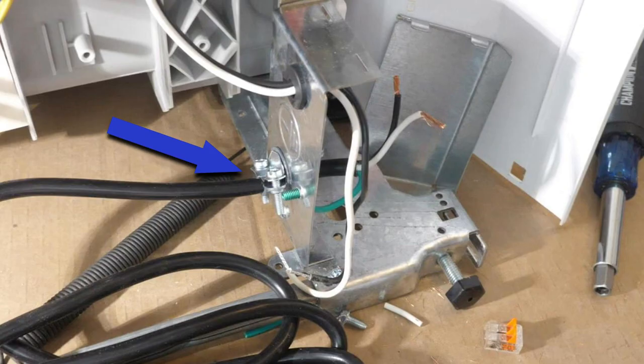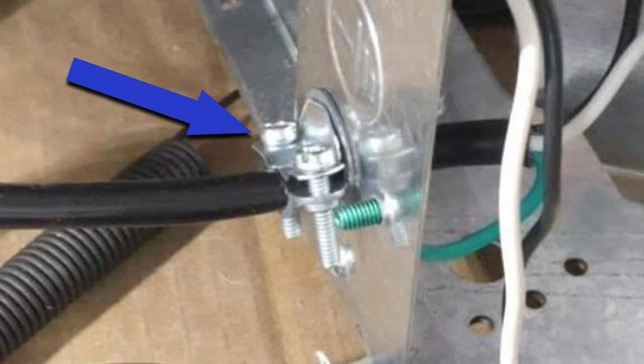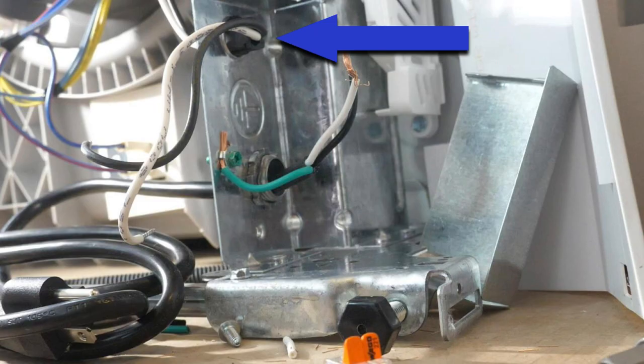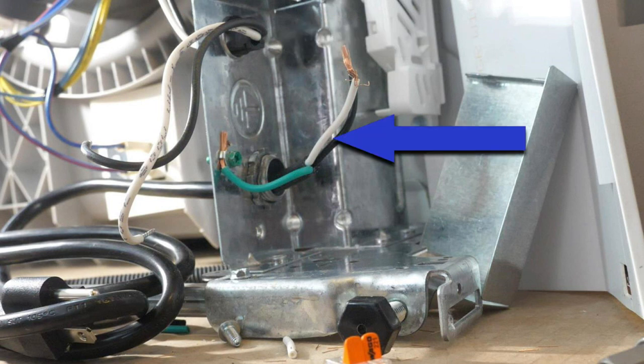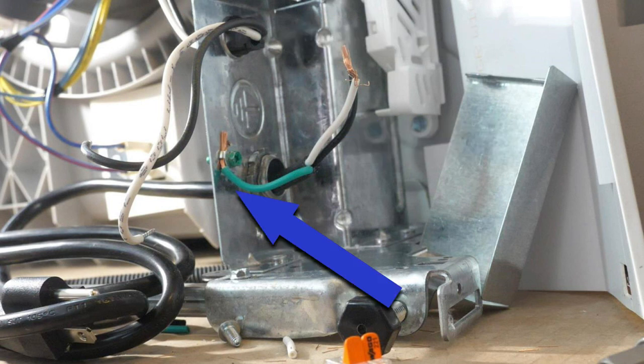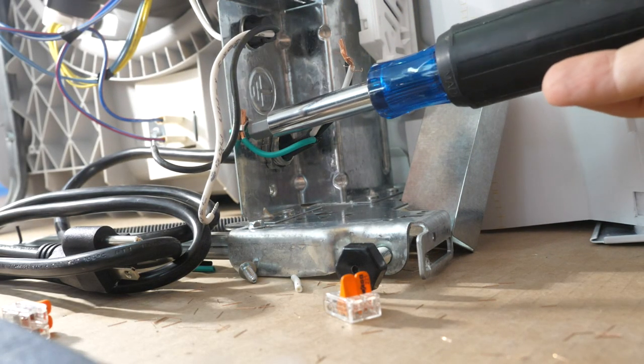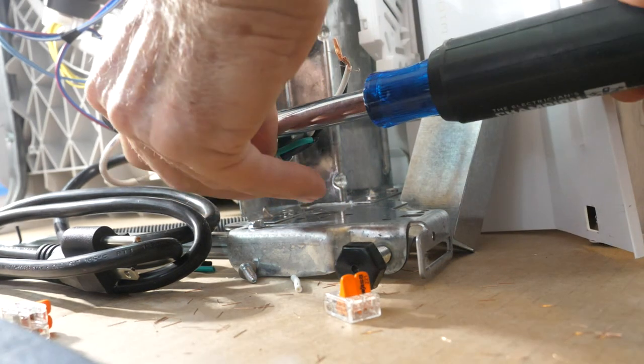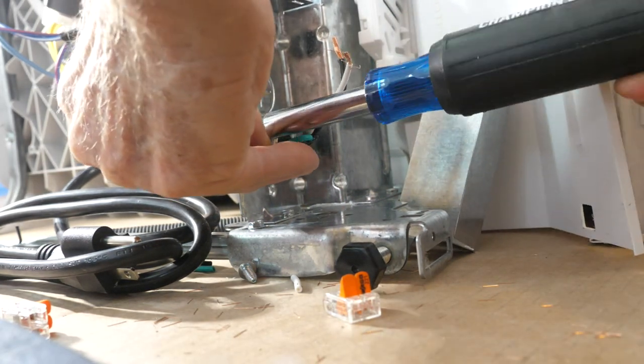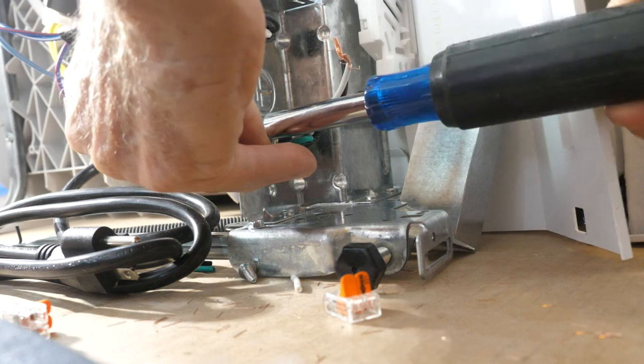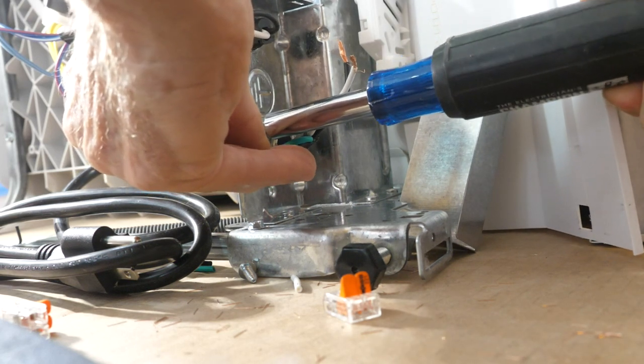Now put your cord right through here. Attach a clamp connector to the box and to the cord. So now we have the hot and neutral from the dishwasher, the hot and neutral from the cord, and the green ground wire from the cord. The green ground wire goes to the green terminal, which is located on the box, and you tighten it down with a 5/16 inch nut driver or a Phillips screwdriver.